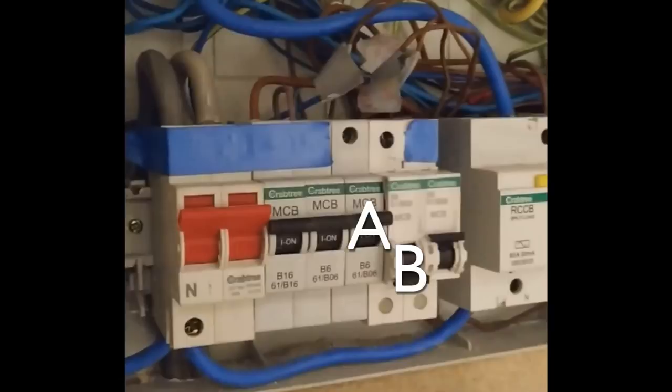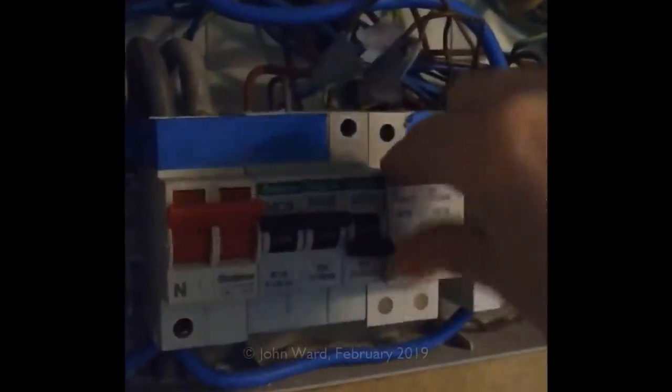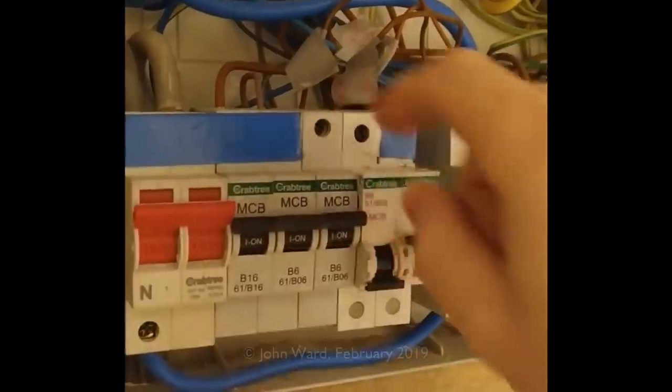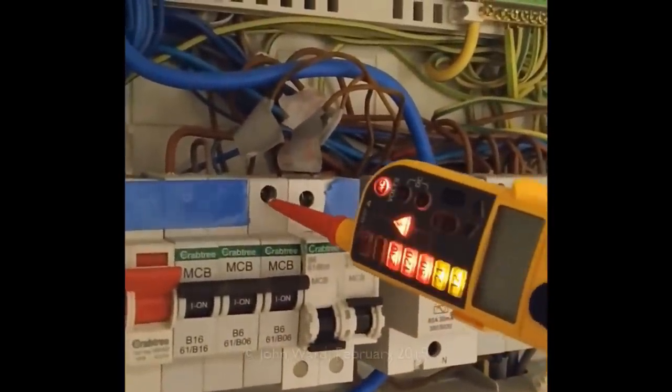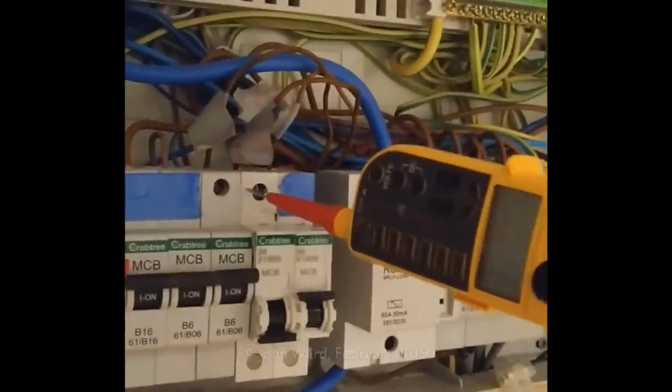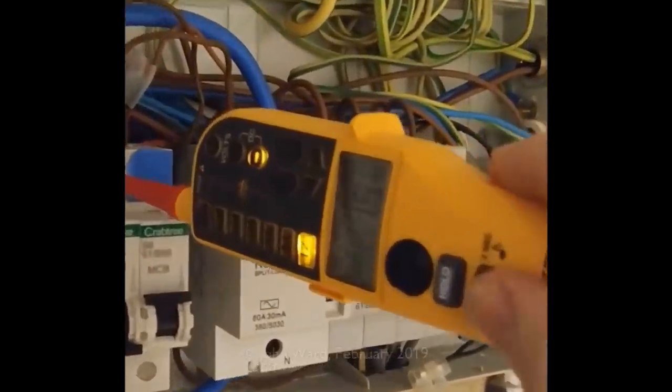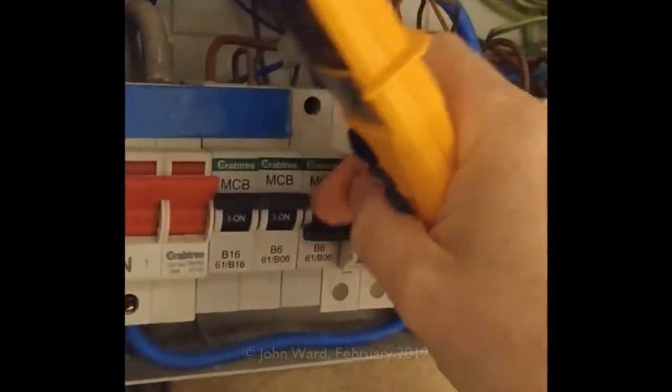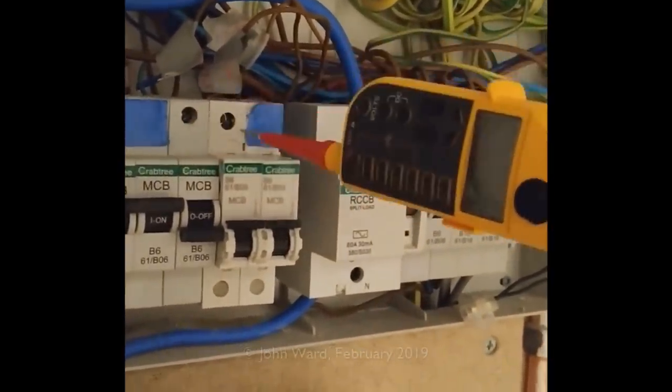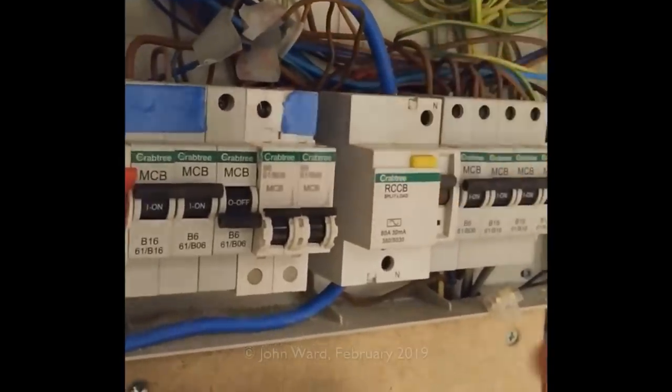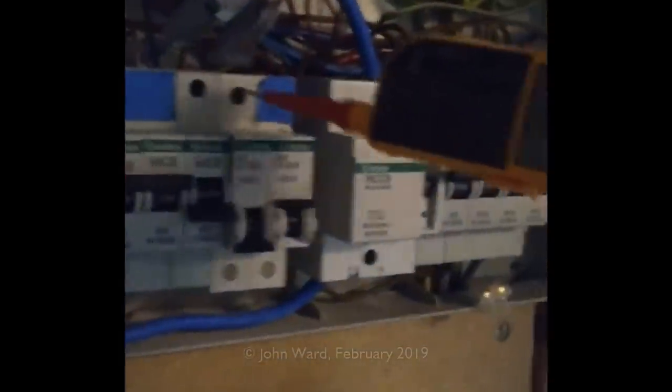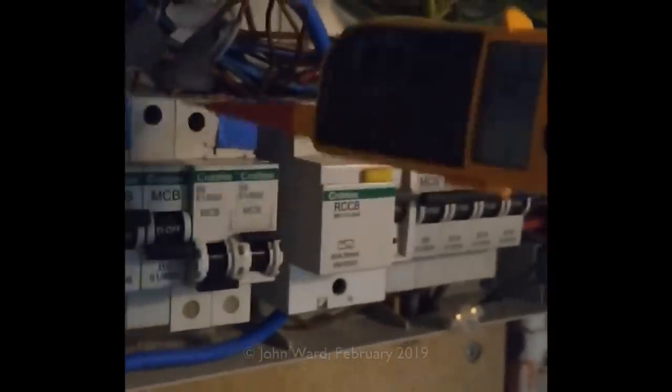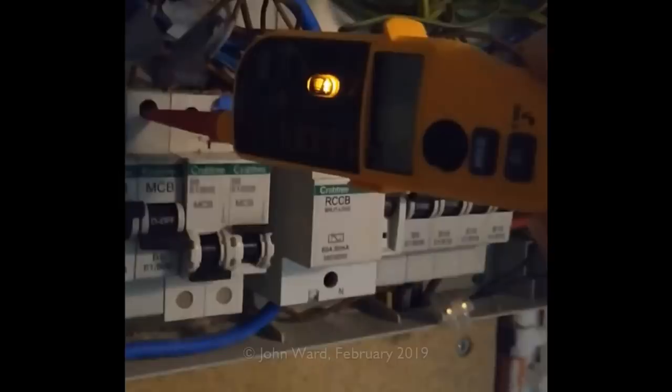Now we can see here that the lights are actually on. So let's just run this video and see what happens when we turn these circuit breakers on and off. So if we turn that one off, the lights go off. But if we turn the other one on, the same lights come on. And then we can just repeat that there. So lights are on basically with either of the circuit breakers on. And if we check the voltage in here, we've got about 240. And we check in here, we don't have anything. We've basically got about 15 volts there, which is apparently a DC voltage from the emergency lighting. And if we turn that one on and the other one off, then we can check in here, and now we've got the 240 in there, and 240 in the other one. And just to final thing there, just checking each one with the power off. You see we're basically getting that 15 volts in one, and nothing in the other.